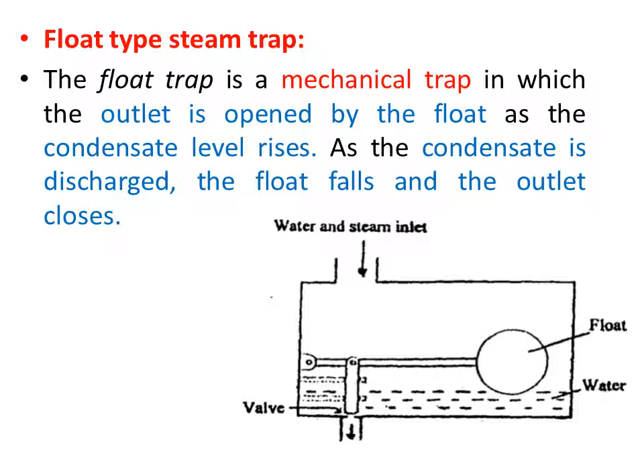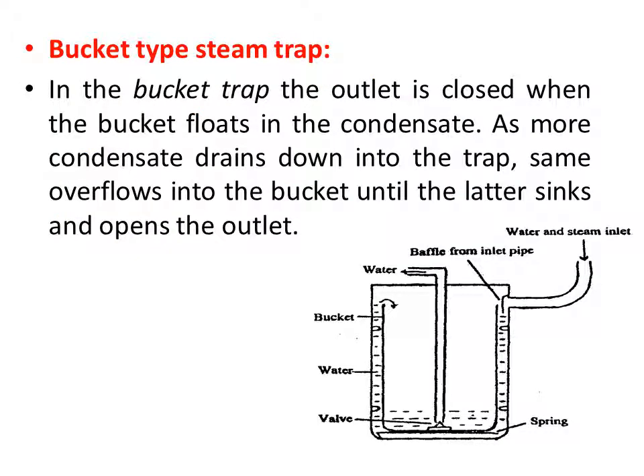The float type steam trap is a mechanical trap in which the outlet is opened by a float as the condensate level rises. When the condensate is discharged, the float falls and the outlet is closed. In the bucket type steam trap, the outlet is closed when the bucket floats in the condensate. As more condensate drains into the trap, it overflows into the bucket until the bucket sinks and opens the outlet.